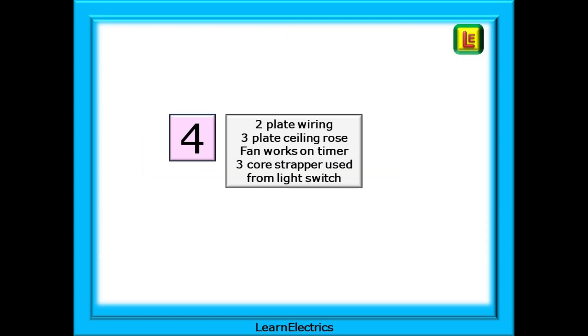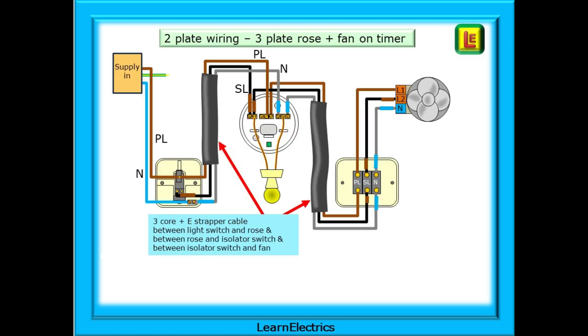Number four is all about two plate wiring and three plate ceiling rose but this time taking a permanent feed from the light switch itself. If it's possible to route a new cable from the light switch to the ceiling rose we can use this method. Here I've shown it as running a new three core strapper cable but it may also be an extra sheathed single to give us the three live conductors that we need. Whichever way we do it we now have a permanent line, a switched line and a neutral available to us to enable the fan and the timer to work.